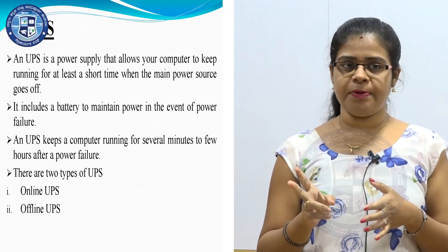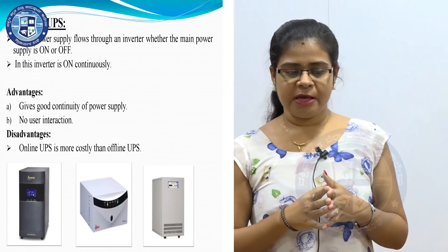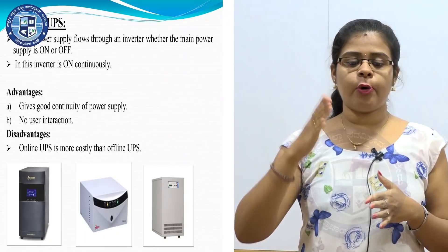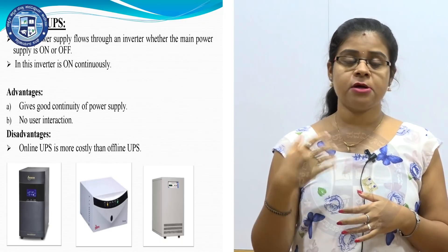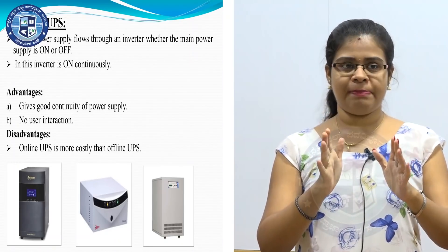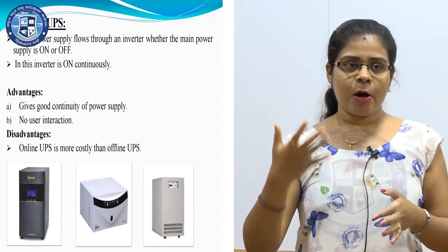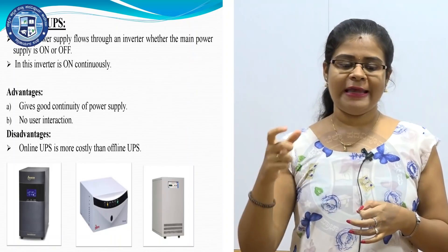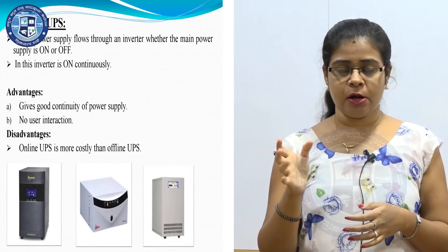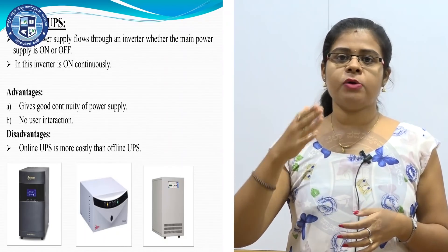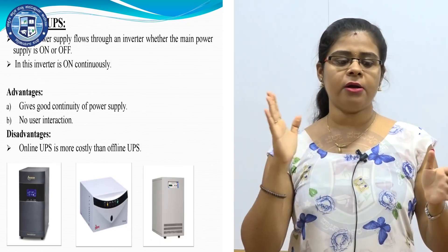There are two types of UPS: online UPS and offline UPS. In online UPS, the power supply flows through an inverter whether the main power supply is on or off. The inverter in an online UPS remains on continuously.